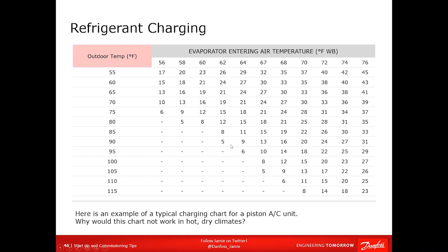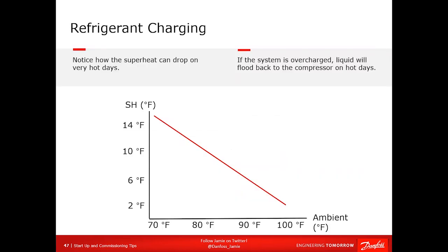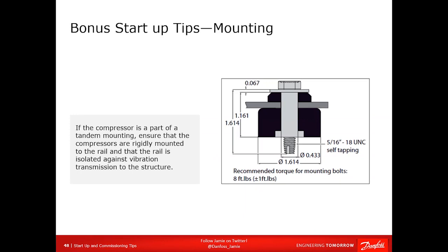Now, remember how I said we cleaned the vegetation away and the condensing temperature dropped 12 degrees? Well, that's why this is a problem. Because if it's 100 degrees outside and 67 wet bulb inside and you put it to 112, you're going to have a flooded compressor. Ditto if you overcharge the system and increase your condensing temperature. So again, these are specific to regional areas. They are affected by outdoor temperatures, and the condensing pressure is affected by charge and how much airflow goes across it. So once again, it is an inverse relationship. As your outdoor temperature goes up, the amount of superheat goes down. You'll also get less subcooling because all your refrigerant is in the evaporator, starving the compressor.